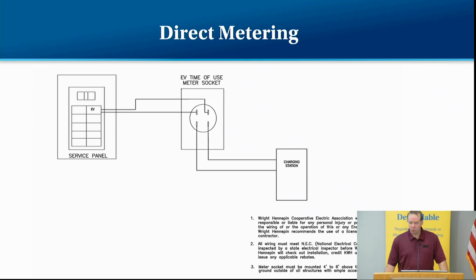Yep, we do provide it, but if they wanted to go with a 200 amp bypass, they could do that to a dedicated sub panel if that was easier, or in a new building installation. We would put some locks on the panel that prevent access, so no other circuits could be added. And we obviously would not want a 30 space panel put in for it. It would be the smallest space panel you could get for the size, and that would serve the needs also.